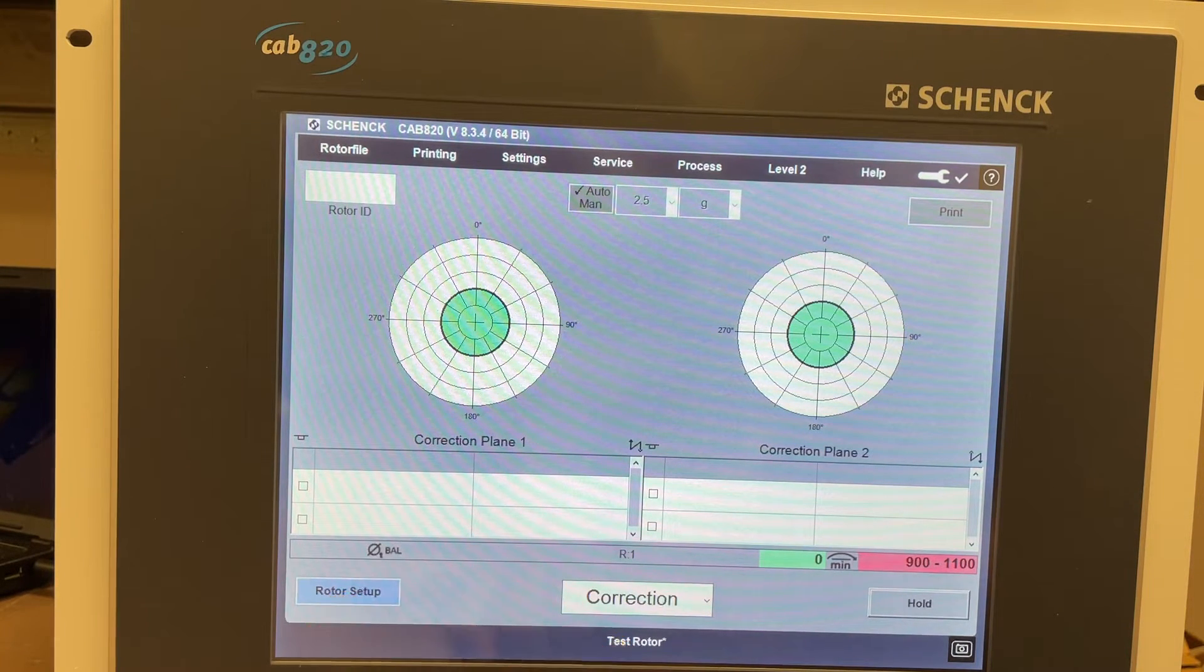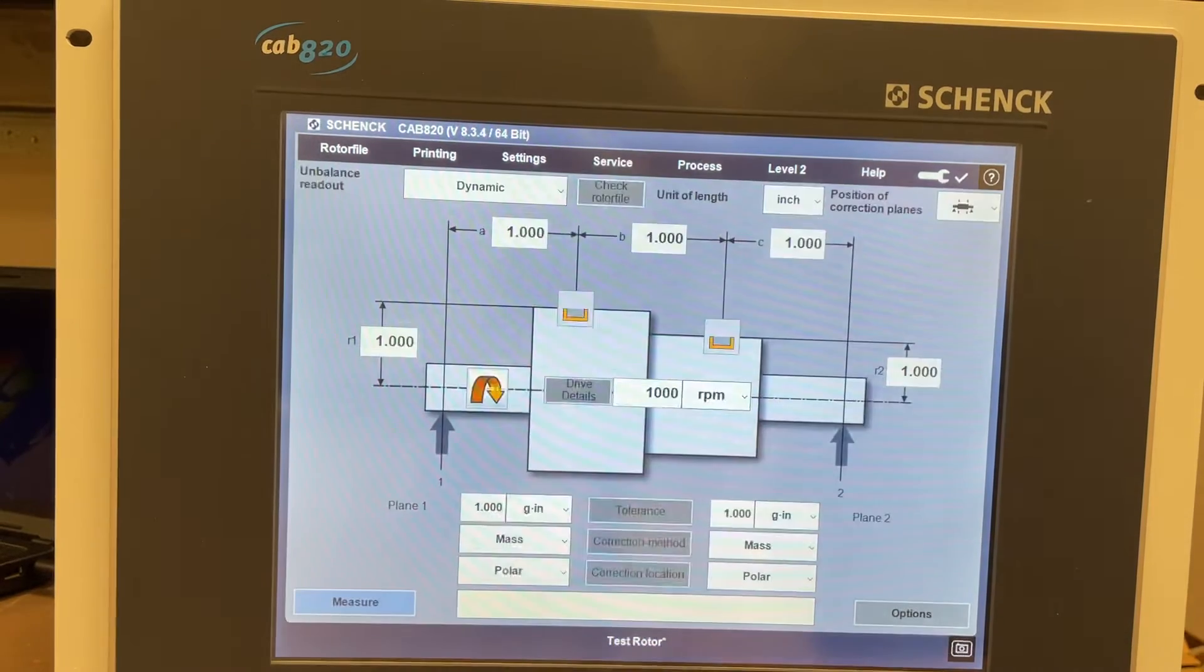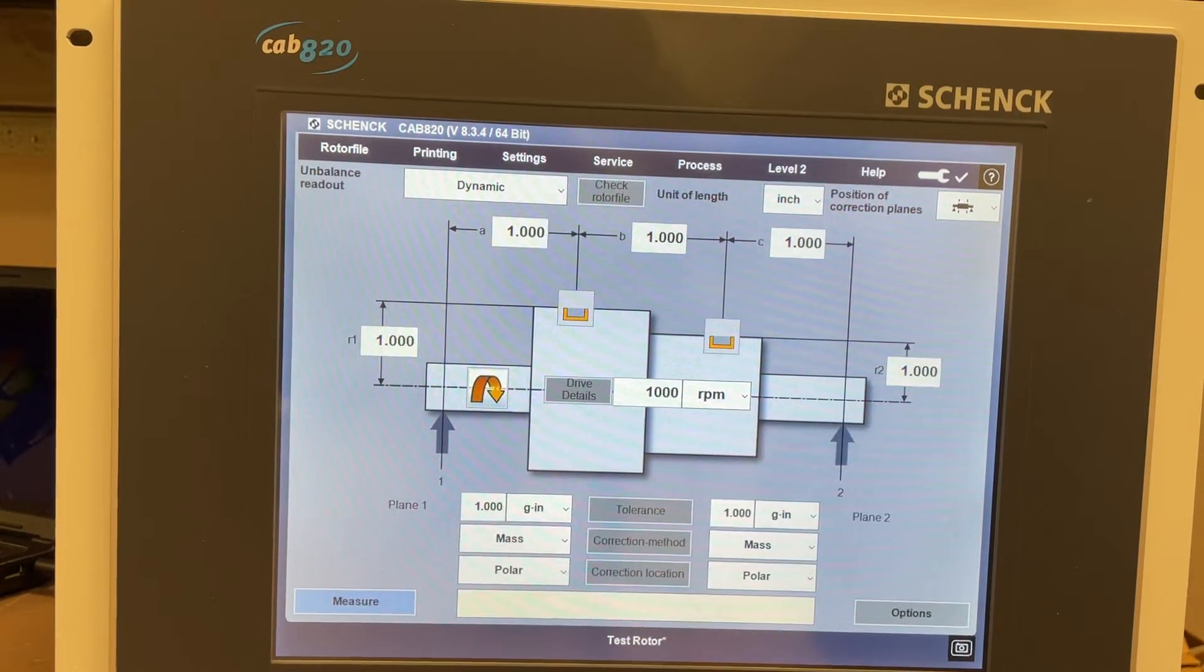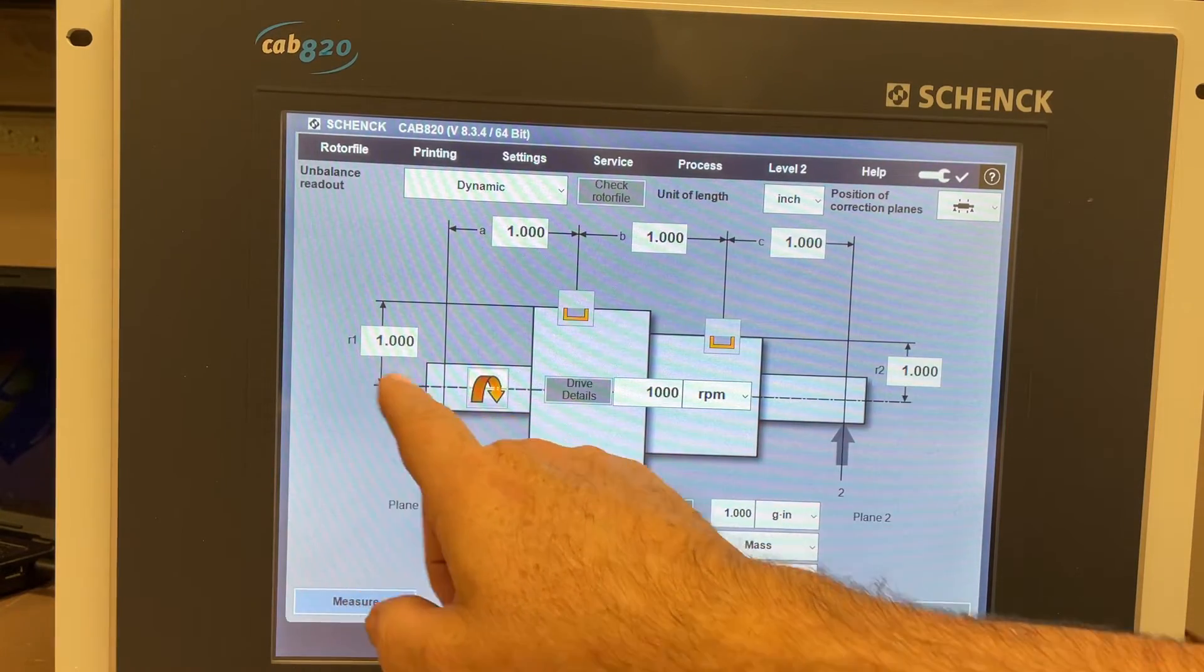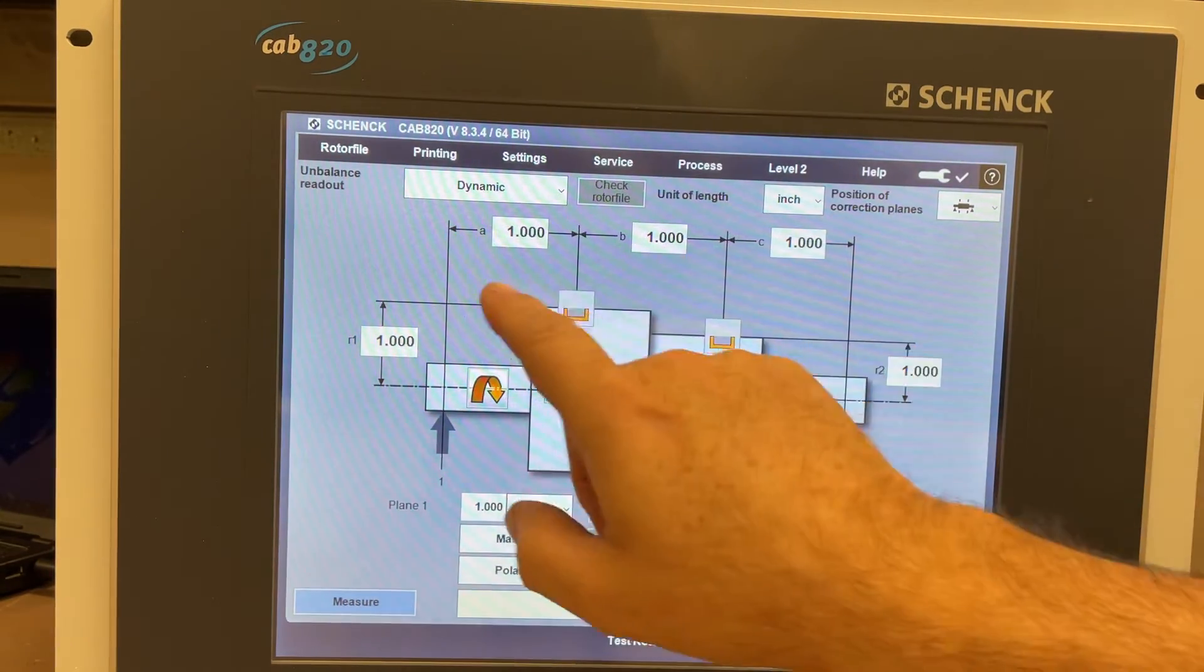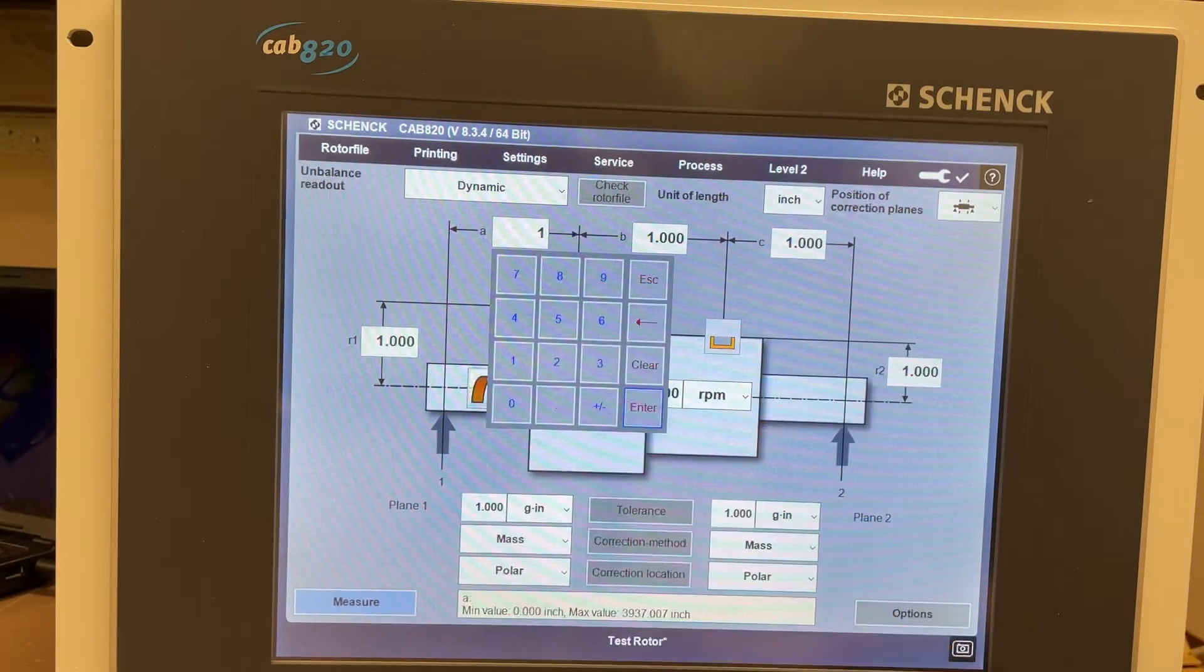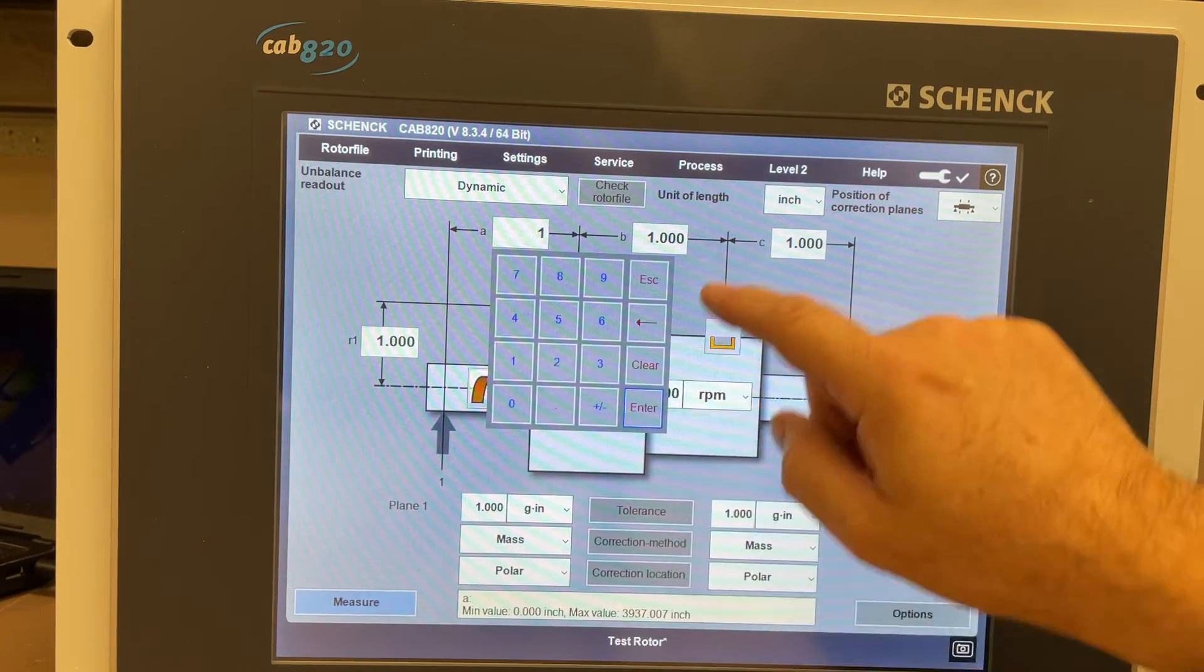In the bottom left, so once you've got your rotor set up in the balancing bed, you can get a tape measure, measure the radius of the shaft, your ABC measurements. So you can actually touch these areas and enter them in numerically.